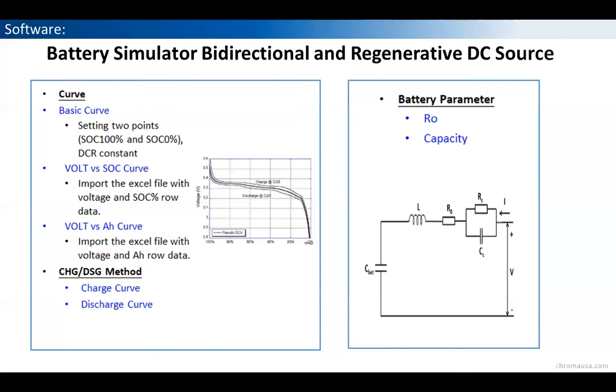With voltage versus state of charge curves, we can take the curve of an actual battery and load it into our software. From there we can control our 62000D, so as the load varies, its voltage will vary per the charging or discharge curve we've loaded in. It truly operates very much like an actual battery. We can even input the internal resistance, the equivalent resistance of the battery, so if you have a specification for a specific battery, we can duplicate those specifications with our bidirectional DC source.